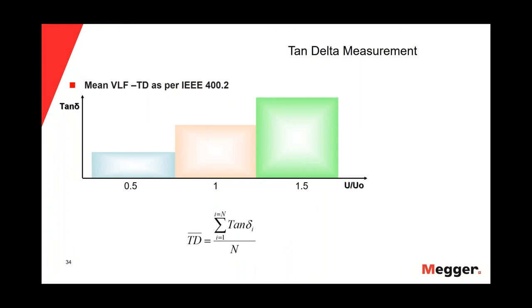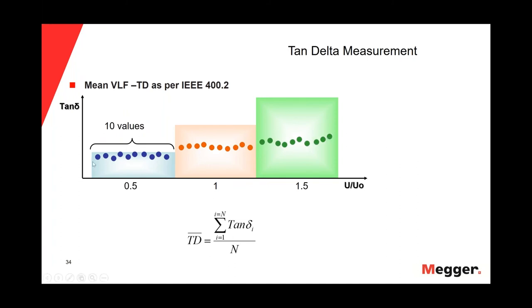The first evaluation criterion is the mean value of the tan delta — we add all the individual values of the tan delta for each voltage step and divide by the number of measurements. In this case 30, because we have 10 measurements at each of the three voltage steps. The second criterion is the delta of the tan delta: the mean value of the tan delta at 1.5 U0 minus the mean value at 0.5 U0.